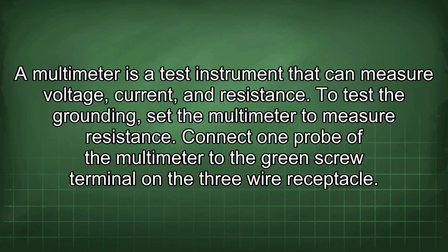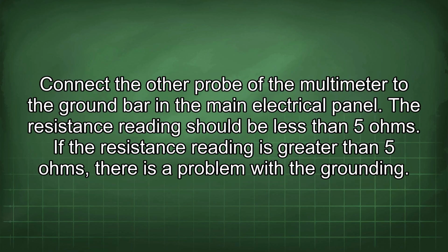Connect one probe of the multimeter to the green screw terminal on the 3-wire receptacle. Connect the other probe of the multimeter to the ground bar in the main electrical panel. The resistance reading should be less than 5 ohms. If the resistance reading is greater than 5 ohms, there is a problem with the grounding.